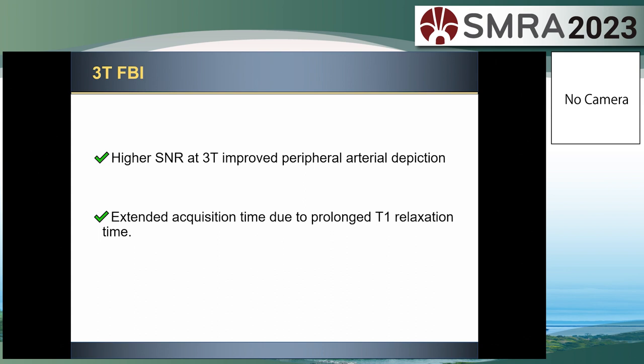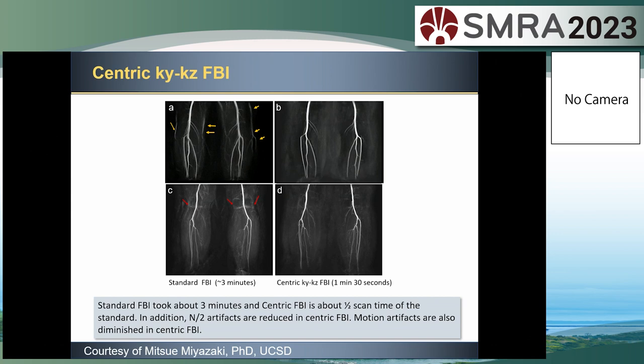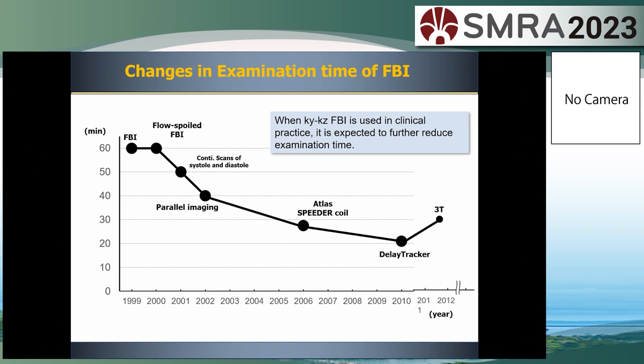However, acquisition time is extended at 3T due to prolonged T1 relaxation time. So a new technique, Centric KY-KZ FBI, has been developed to further reduce acquisition time. Standard FBI took about three minutes, and Centric FBI takes about half the scan time of the standard. In addition, N/2 ghosting artifacts are reduced in Centric FBI, and motion artifacts are also diminished. When Centric KY-KZ FBI is used in clinical practice, it is expected to further reduce examination time.